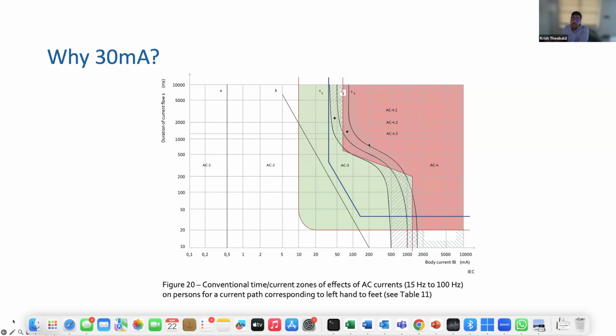Why 30 milliampere? Aside from the effects of ventricular fibrillation, there is something called muscular contractions. The standard says that the effects of muscular contractions are either tolerable or non-tolerable. So there is a further division on the graph into a green zone and a red zone. In the green zone, you have a tolerable risk of muscular contractions, and in the red zone, a non-tolerable risk. When you use a 30 milliampere RCD, as you can see in this blue line, you are restricting yourself to a tolerable risk of muscular contractions. Remember, RCDs cannot limit the amount of current, they can only limit the time. So when you use a 30 milliampere RCD, you're limiting time such that you have a tolerable risk of muscular contractions and no risk of ventricular fibrillation. That's why 30 milliampere is suitable.